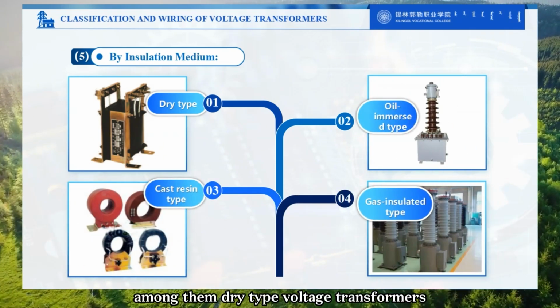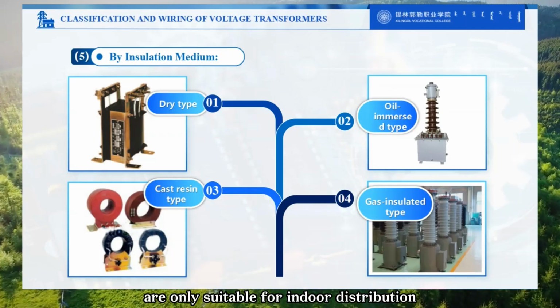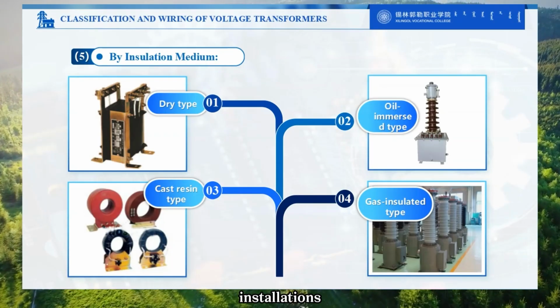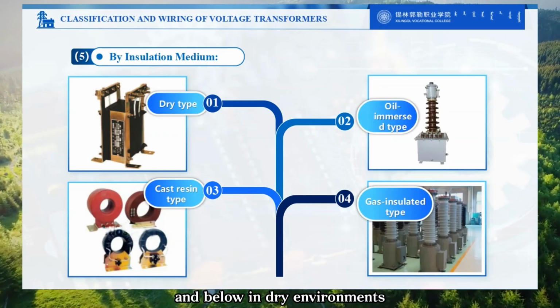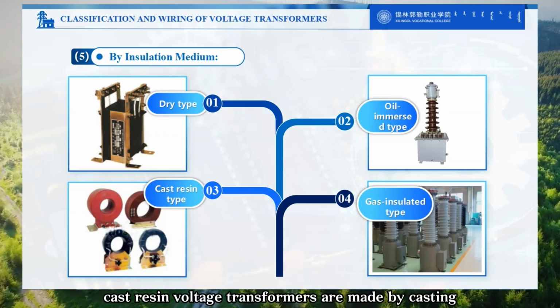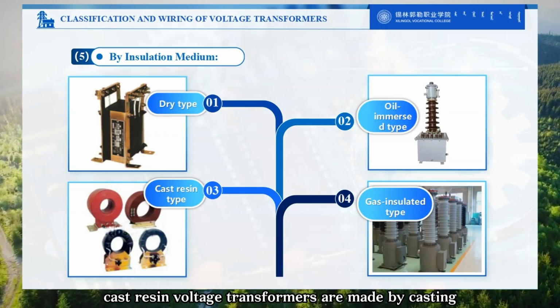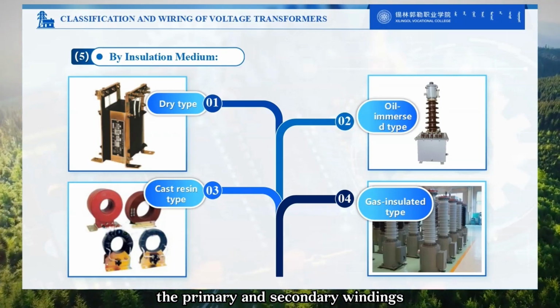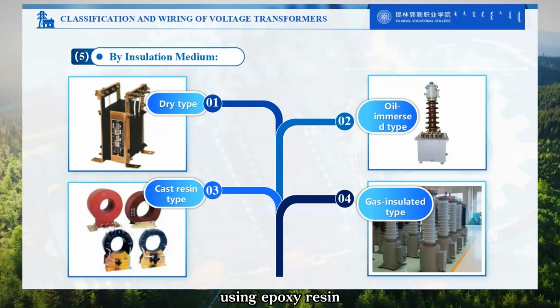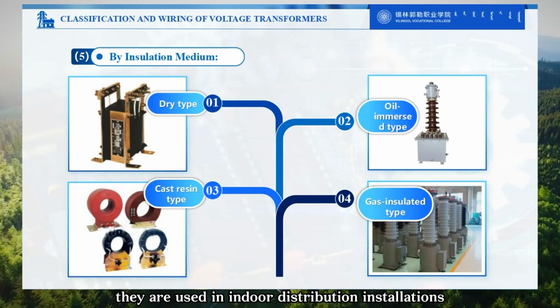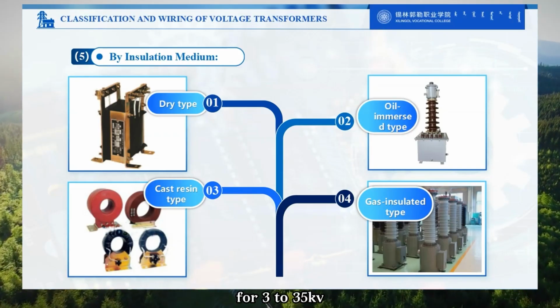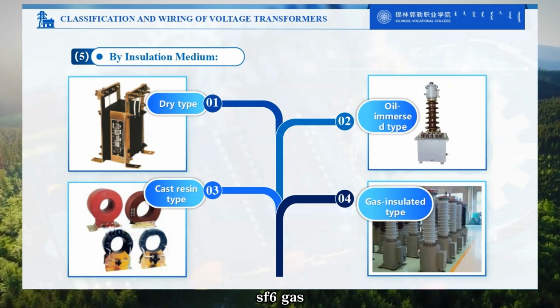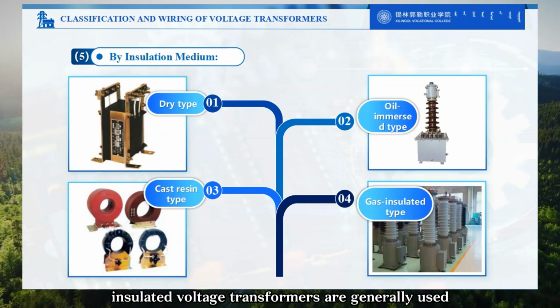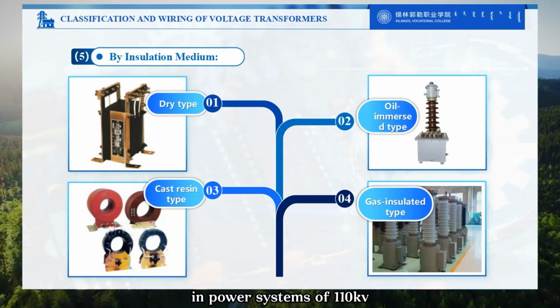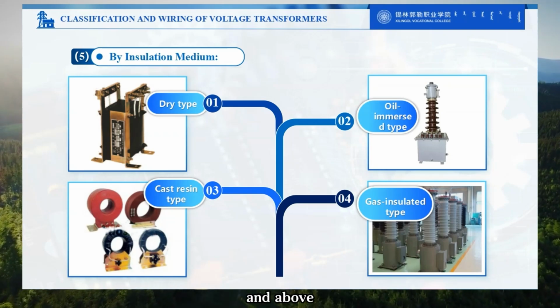Among them, dry-type voltage transformers are only suitable for indoor distribution installations at 6 kV and below in dry environments. Cast resin voltage transformers are made by casting the primary and secondary windings together with the leads into a mold using epoxy resin. They are used in indoor distribution installations for 3 to 35 kV. SF6 gas-insulated voltage transformers are generally used in power systems of 110 kV and above.